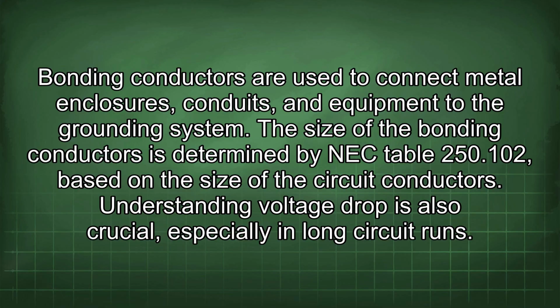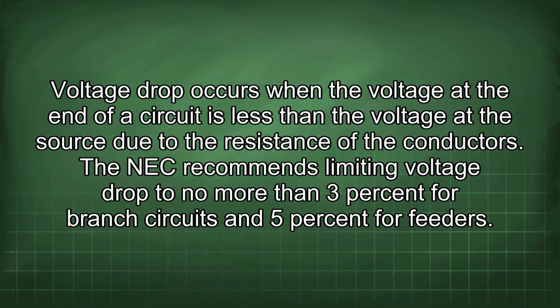The size of the bonding conductors is determined by NEC Table 250.102 based on the size of the circuit conductors. Understanding voltage drop is also crucial, especially in long circuit runs. Voltage drop occurs when the voltage at the end of a circuit is less than the voltage at the source due to the resistance of the conductors.